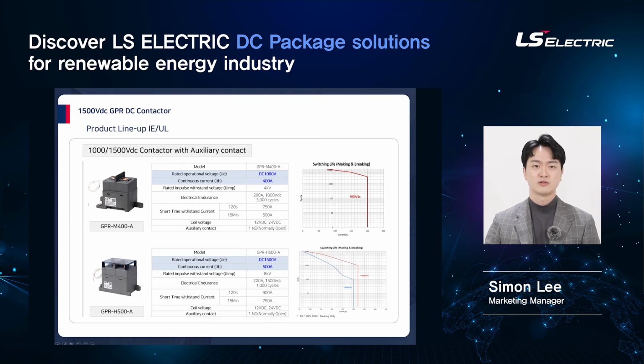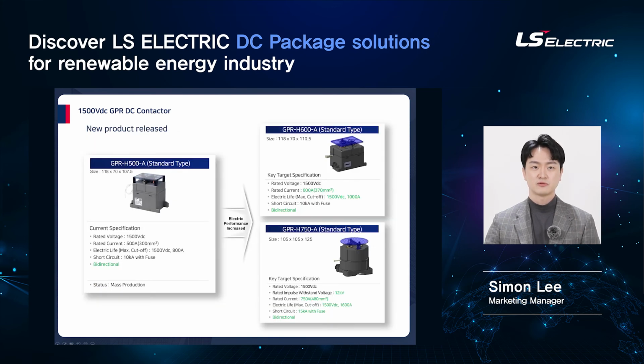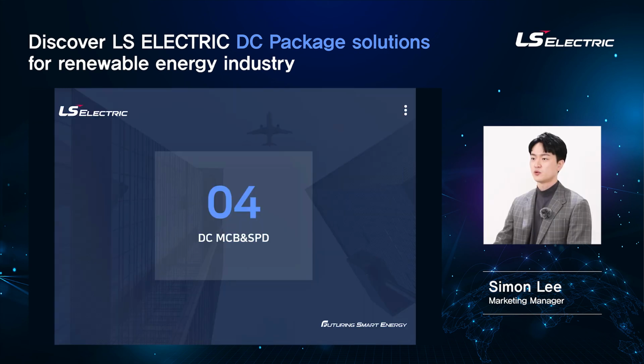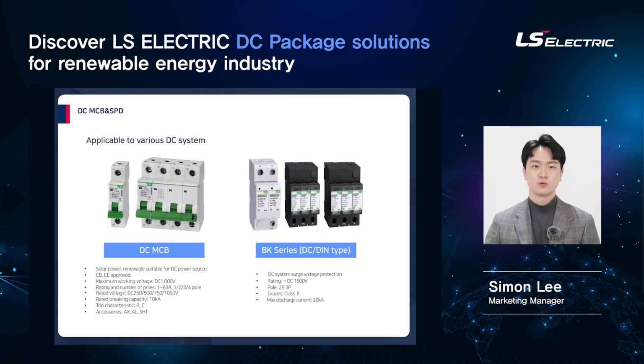GPR M400A and H500A are the most common DC contactors widely used in industrial application at this moment. Each contactor is for 1000 volts and 1500 volt system, including auxiliary contact, which is used for main contact status detection. I would like to end up with our new product released. These are H600 and H750 for 1500 volt system with higher ampere rating. These will be the solutions for battery manufacturer who request higher capacity of ESS. Also, we have DC lineup for MCB and SPD, which are normally applied with those DC products we deal with in early slides.